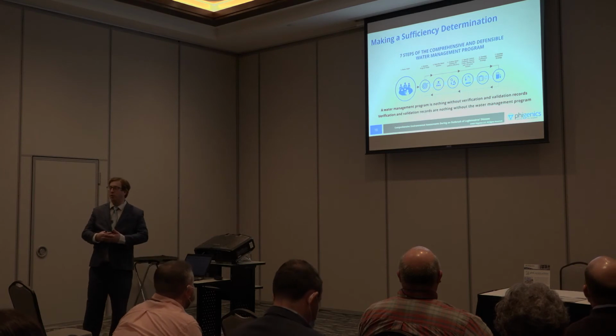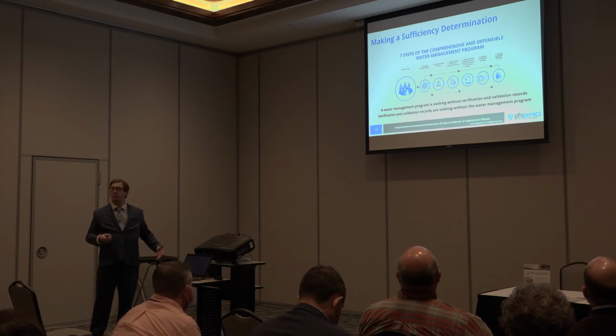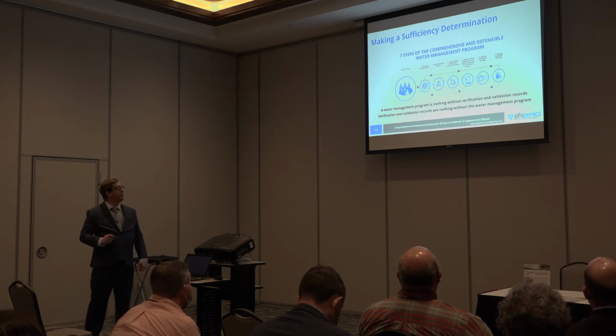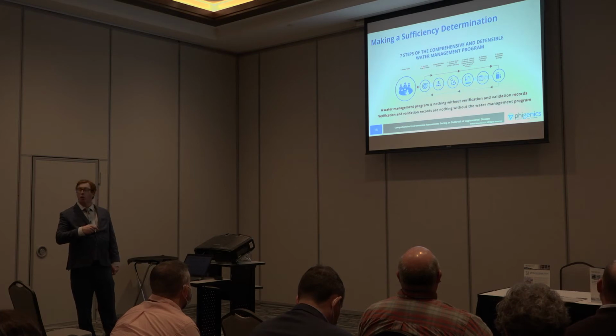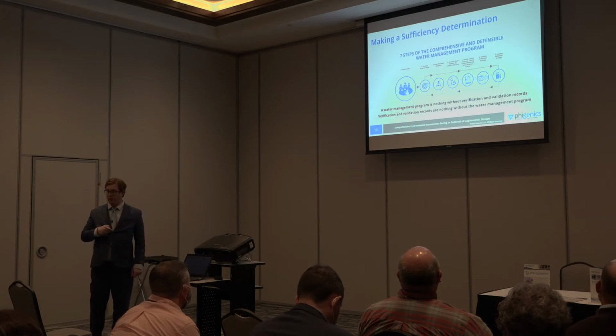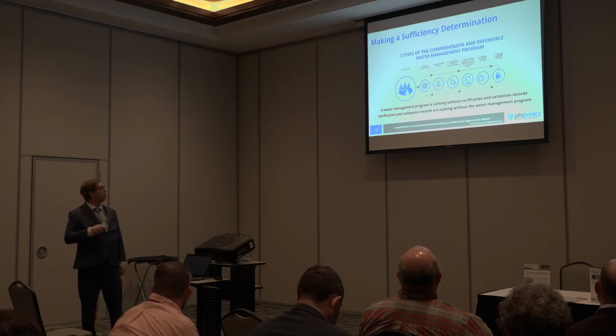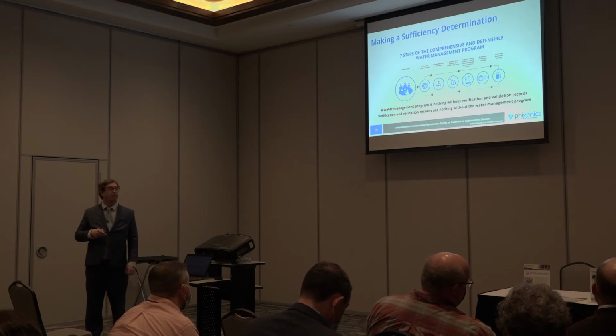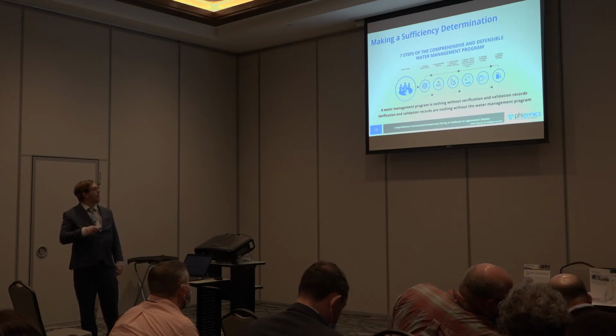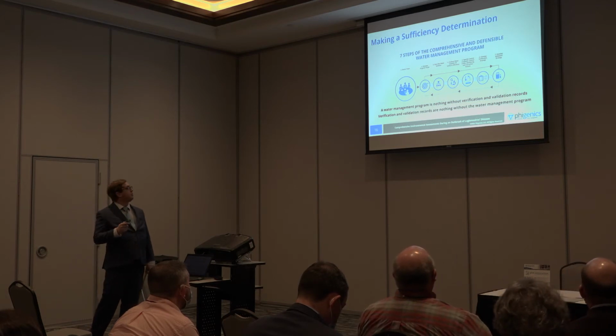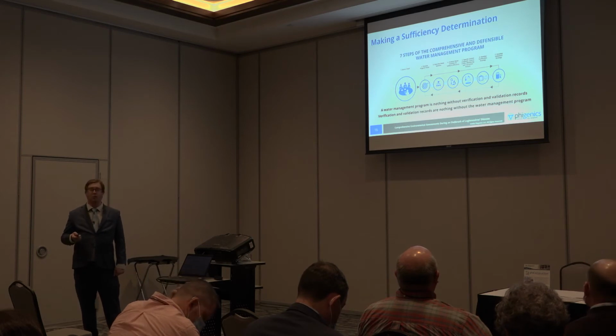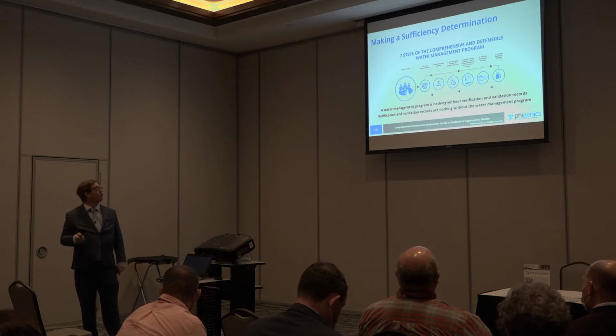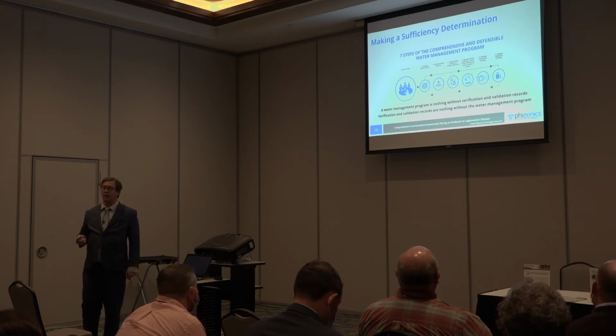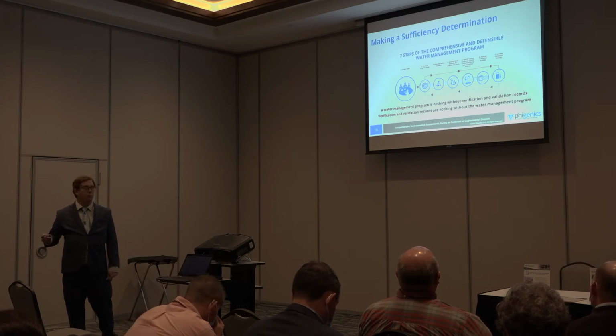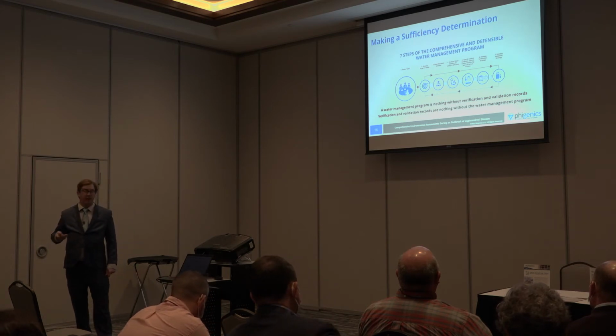First and foremost, the water management program should include the 7 steps of a comprehensive and defensible water management program, which starts with forming a team, developing program goals, describing the water systems in the building, similar to that list that we saw that CMS put out, analyzing the water systems for safety and efficiency, and also the potential for hazard growth and hazardous condition accumulation, specifying control locations, control limits, monitoring, and corrective actions, developing a verification strategy, and then developing a validation strategy. Verification means making sure that the program is implemented as designed. Validation, we mean, is that the program is effective as designed.